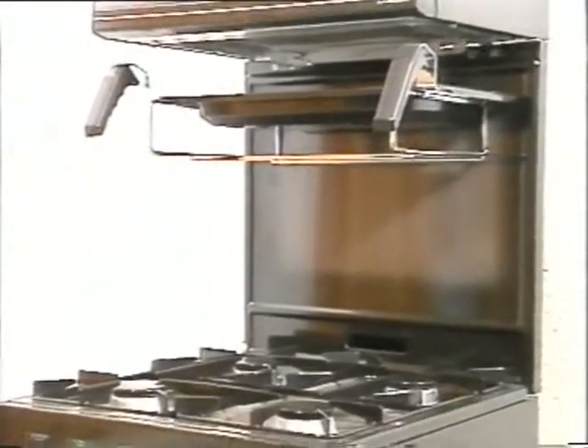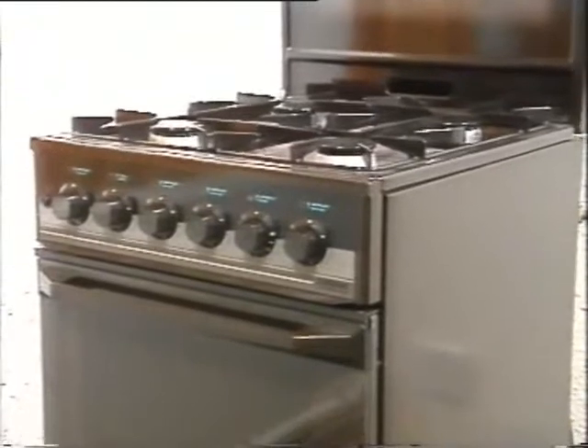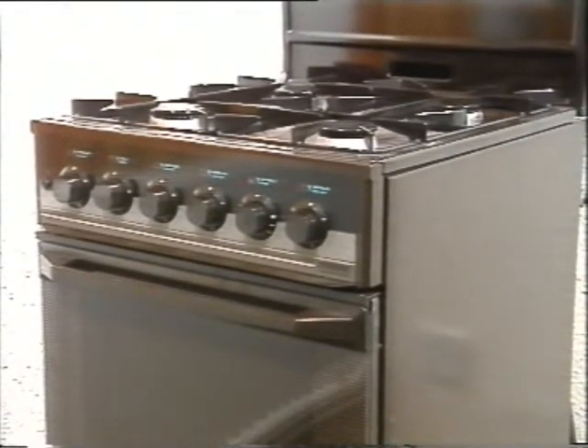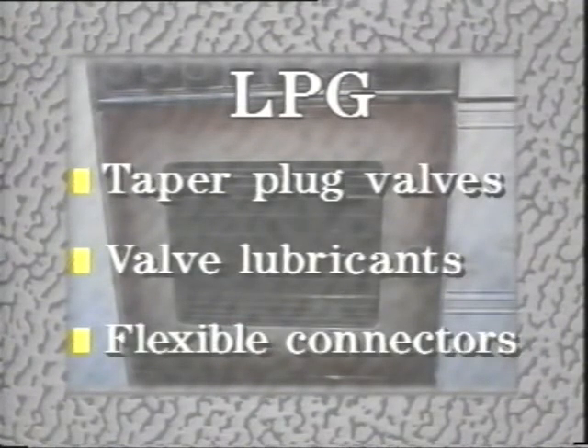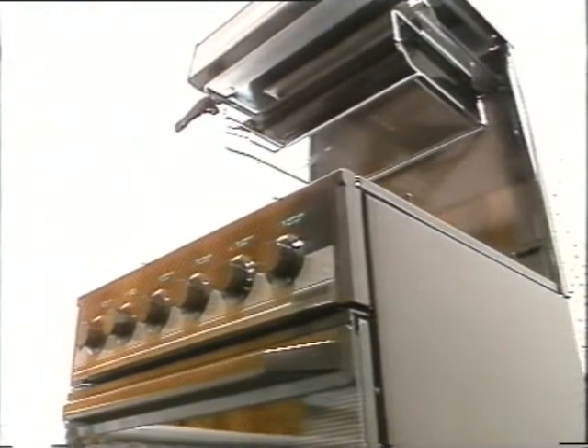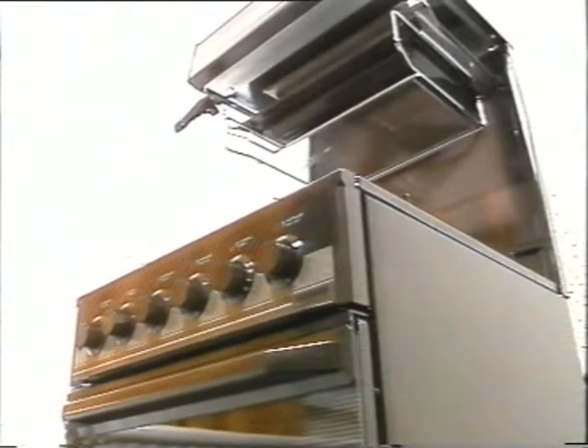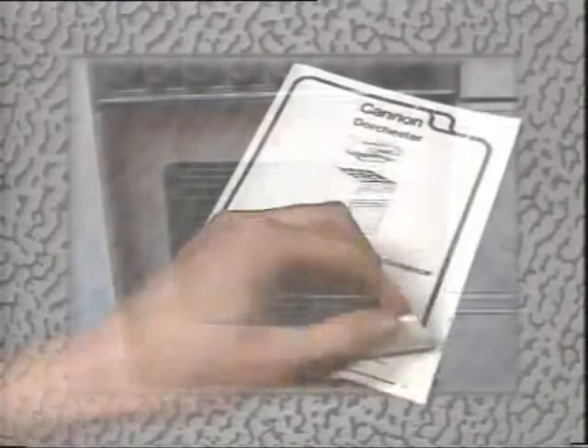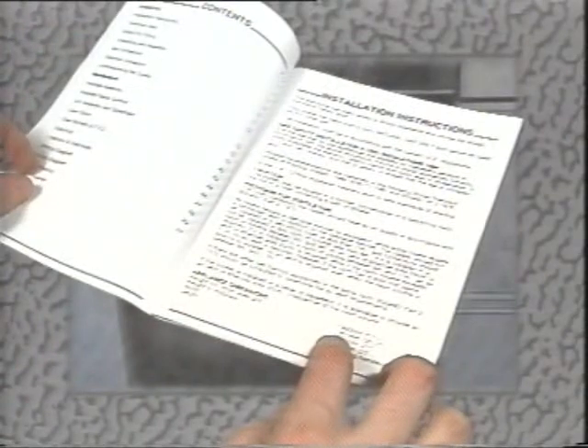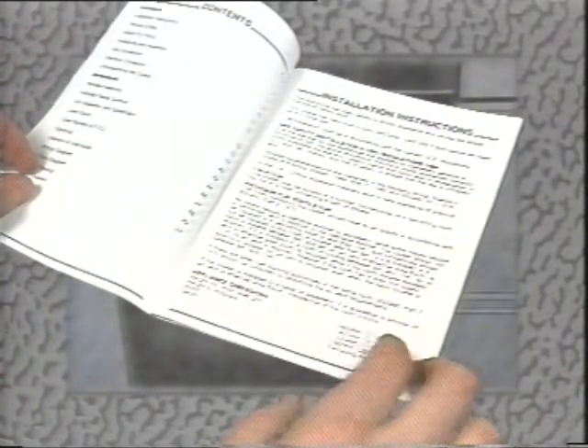As we've already said, appliances fueled by liquefied petroleum gas need different fittings and have their own distinct BS regulations. Special taper plug valves, valve lubricants and flexible connectors are needed for liquefied petroleum gas. Appliances which use this type of fuel can't be installed in cellars or basements, and if they're installed in a caravan or some other non-permanent dwelling, there are special ventilation requirements. As we indicated right at the start, all appliances and installations must conform with BS regulations and manufacturer's instructions. If you're ever in doubt, or even if you're not, always check them.